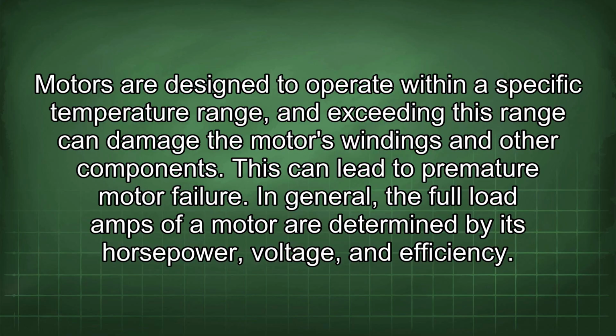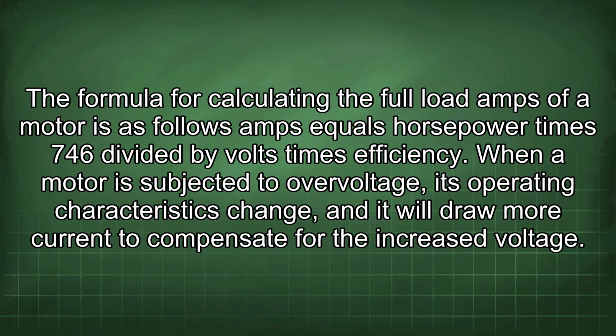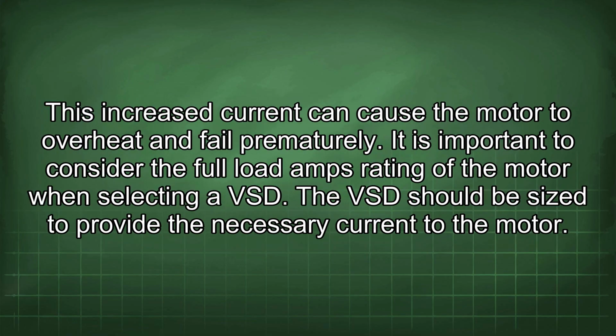In general, the full load amps of a motor are determined by its horsepower, voltage, and efficiency. The formula for calculating the full load amps of a motor is as follows: amps equals horsepower times 746 divided by volts times efficiency. When a motor is subjected to overvoltage, its operating characteristics change, and it will draw more current to compensate for the increased voltage. This increased current can cause the motor to overheat and fail prematurely.